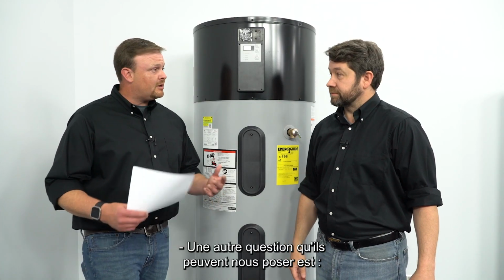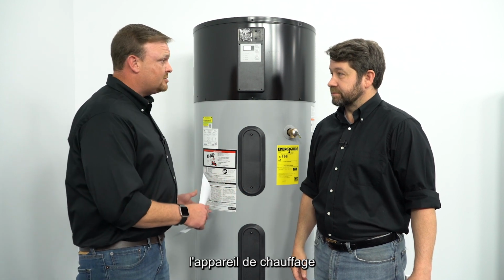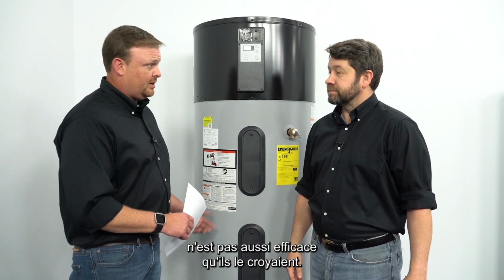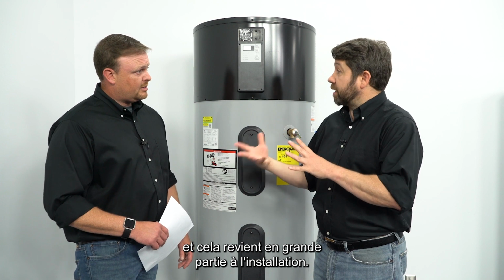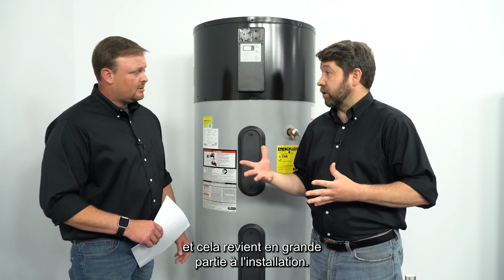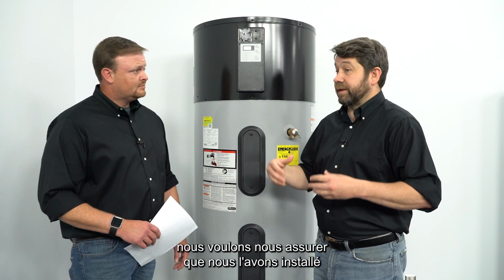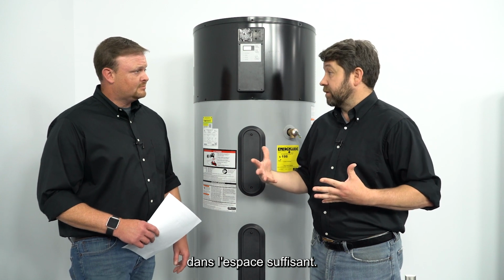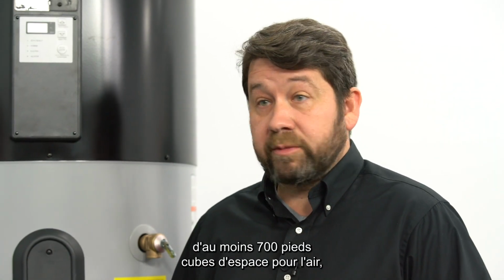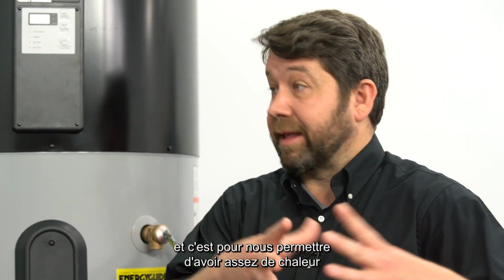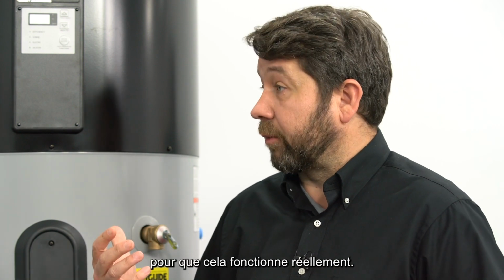Another question that they may ask us is, the heater's not as efficient as they thought it should be. And that comes back to largely how it's installed. Right. So the first thing we want to make sure is that we've got it installed in a big enough space. We need at least 700 cubic feet of space for air, and that's to allow us to have enough heat for this to actually operate.